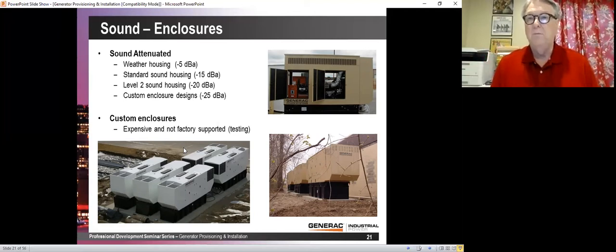Now, typically you measure the sound on all four sides and you average. One manufacturer now is measuring the sound on 8 sides, so that would be the 4 sides and the 4 corners. Now that might sound better. In reality, all that does is allow them to quote quieter sound ratings because on the corners, the sound is lower, and therefore by measuring on the 4 corners, you can publish a dBA level that is lower than what that same generator would produce if you just measured the 4 sides. Generac does the 4 sides.